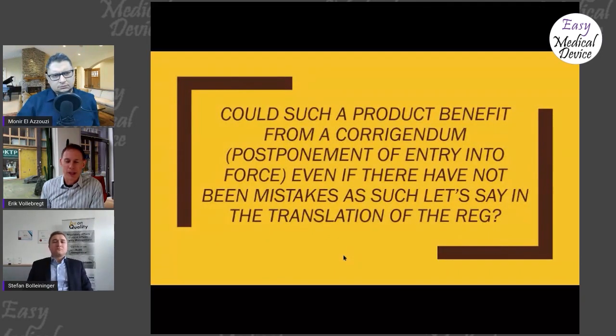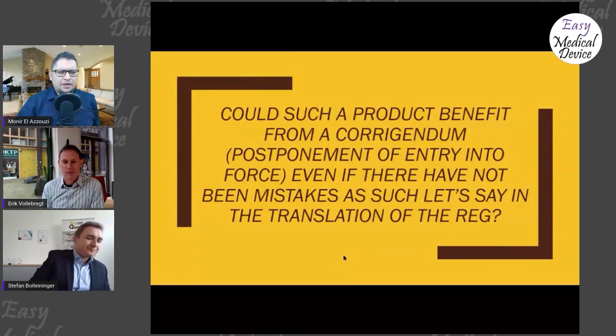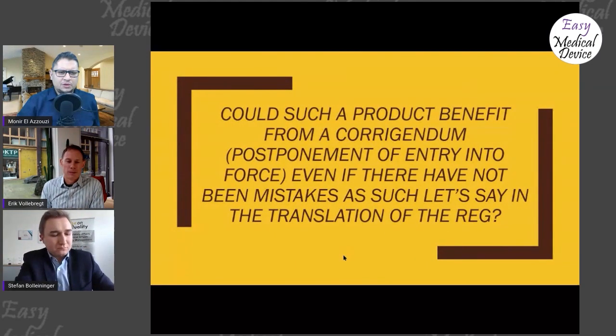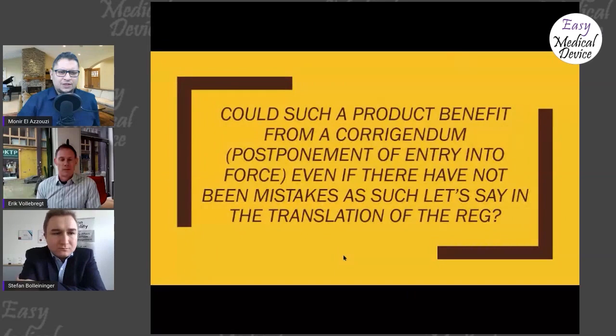But if you're not a medical device at this moment, then as soon as the common specifications enter into force, you have 6 months to get your certificate, and that's also what Stefan impressed. That's why it's relevant now to already get your foot in the door with a notified body, because otherwise you will never make it to a certificate in time. As we said on some episodes with Stefan, we tried to evaluate how long it takes to get a certificate, and for now we arrived at about 1 year, because to get a time slot with some notified bodies can take up to 1 year.